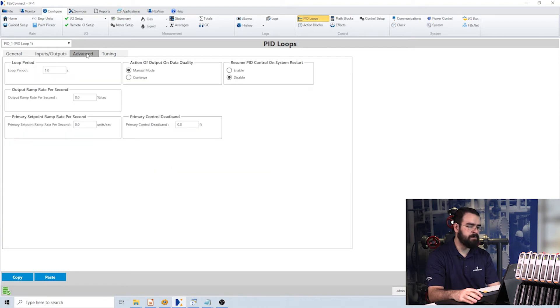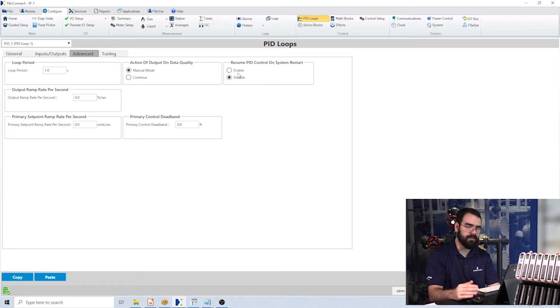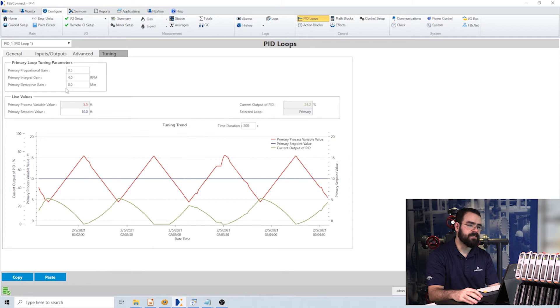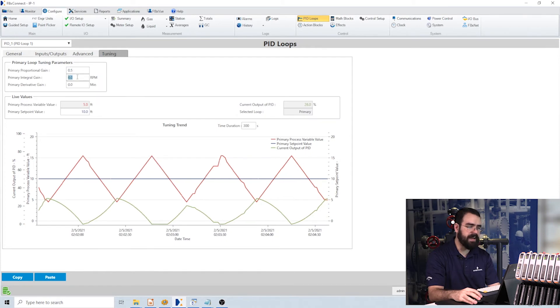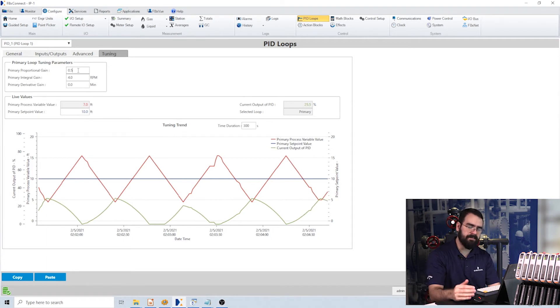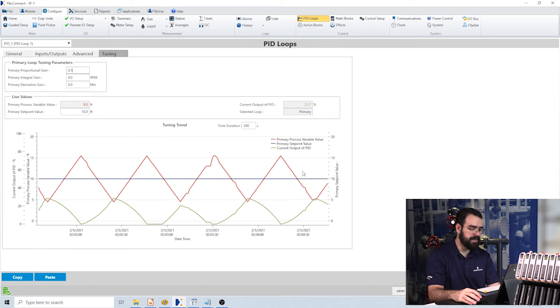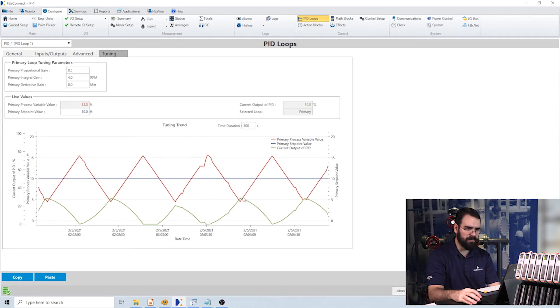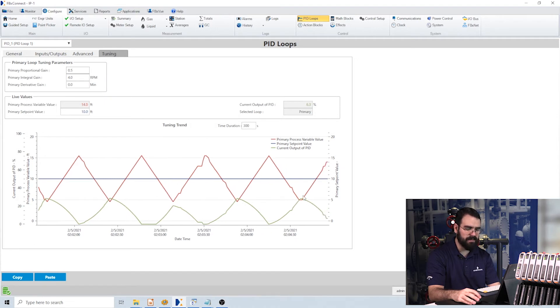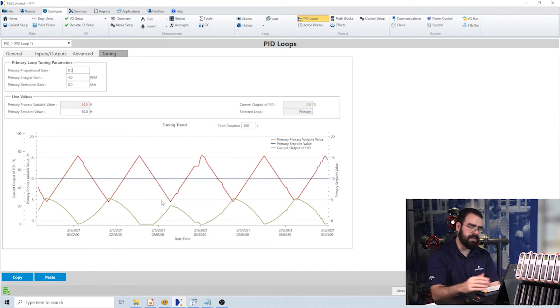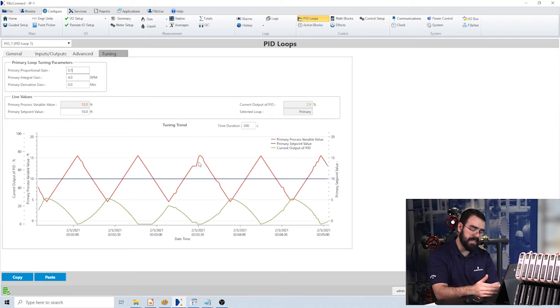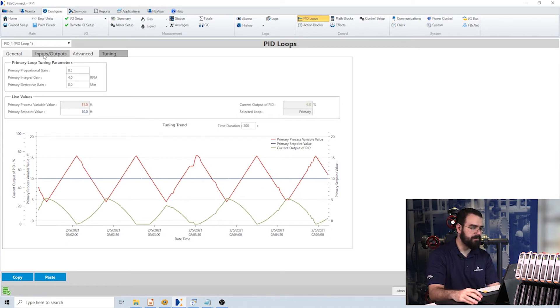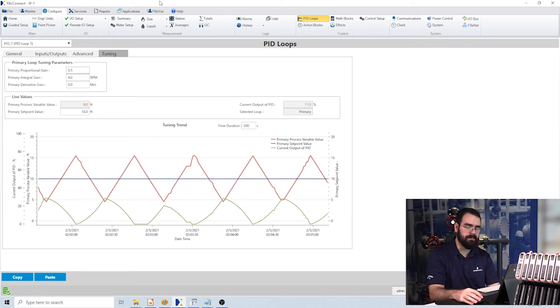Going to the Advanced tab, the PID loop has properties for what happens if our data goes bad due to a communications error, or what happens on restart — whether to keep going or disable the loop. The last tab is the Tuning tab, where you tune your P, I, and D parameters to give your loop the speed or behavior characteristics you want. In the trend, we're showing the process variable, the set point, and the current output. As my process variable — my tank level — goes up and down, the output goes up and down with it. In this case, the PID loop output isn't actually changing our process variable, so we're not nearing the set point; I'm just showing it as an example while my other controls handle it.